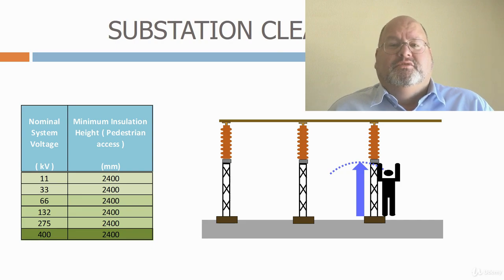Most utilities will define the minimum distance to the bottom of an insulator, in addition to the normal ground and phase clearances. Although the voltage at the bottom of the insulator should in theory be zero, there is still a danger that tracking has occurred down the outside of the insulator due to pollution or rain, and you don't want people touching the bottom of the insulator if this is the case.